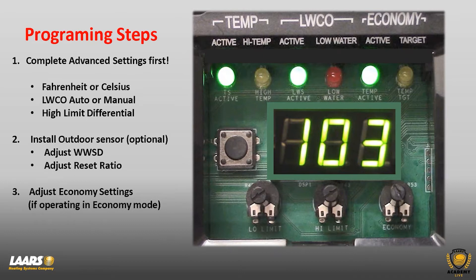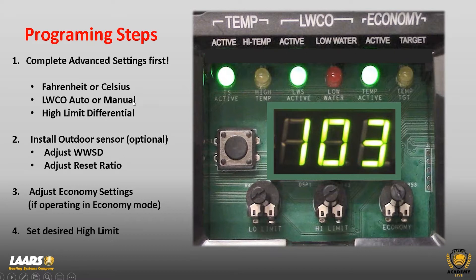Step three is adjusting the economy settings. If you're not utilizing step one or two, skip those and go right to step three: adjust economy settings for thermal targeting. Lastly, set your desired high limit. The reason it's last is that the middle dial is a potentiometer — if you set it for 200 degrees, then make other changes and have to turn it again, your high limit may shift to 160, causing short cycling. So the high limit is always done as the last step.